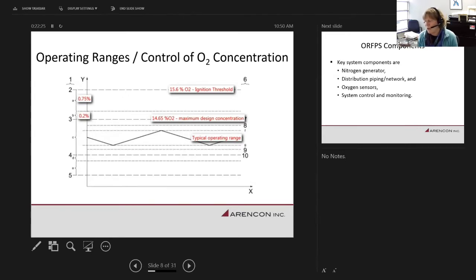And in this case, the markups on here were put in for the project installation in Manitoba. So these were the oxygen concentration levels that we had to achieve within the warehouse where the system was installed in Manitoba. The first step down, the 0.75, represents the safety factor that's mandated by the European norm. That is an absolute. The 0.2% represents the variance, the accuracy of the oxygen sensors in the space.